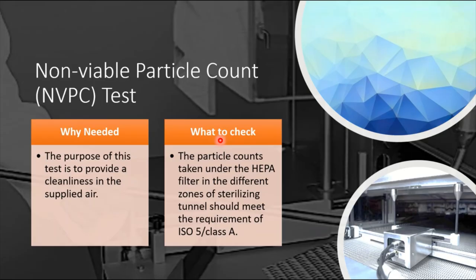Non-viable particle count: the purpose is to prove the cleanliness of the area. What need to check: we need to verify and address that the area fulfills the criteria of ISO 5 or Grade A requirement. Lots of accessories are available. You can do it with long tubing with a cup, and this automation is talking about how we can verify NVPC.